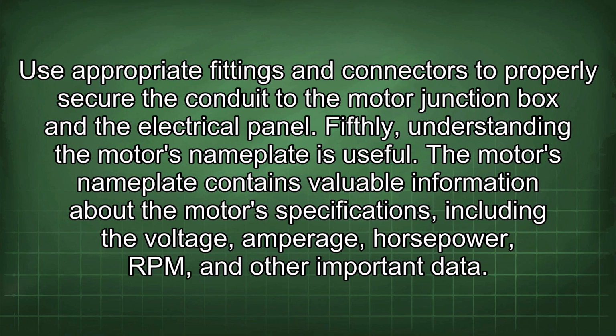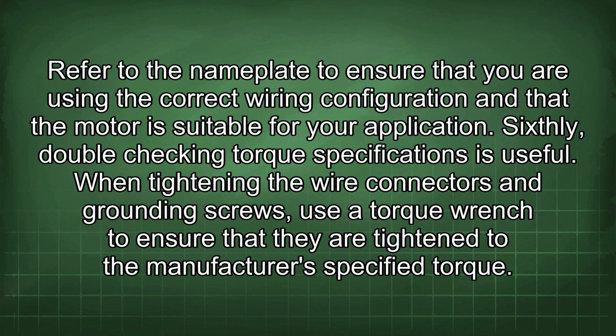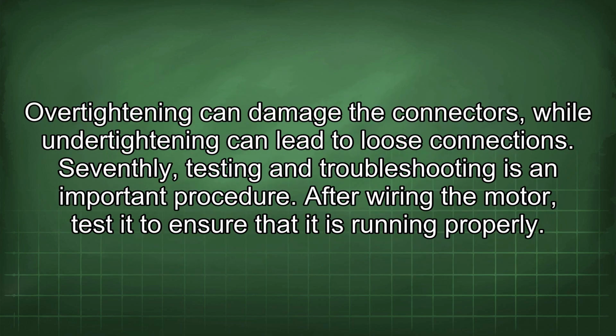The motor's nameplate contains valuable information about the motor's specifications, including the voltage, amperage, horsepower, RPM, and other important data. Refer to the nameplate to ensure that you are using the correct wiring configuration and that the motor is suitable for your application. Sixthly, double-checking torque specifications is useful. When tightening the wire connectors and grounding screws, use a torque wrench to ensure that they are tightened to the manufacturer's specified torque. Over-tightening can damage the connectors, while under-tightening can lead to loose connections.